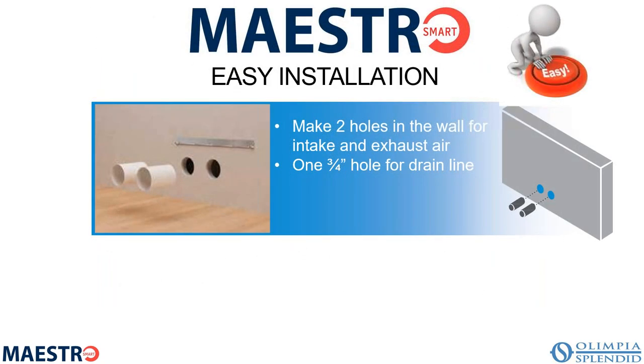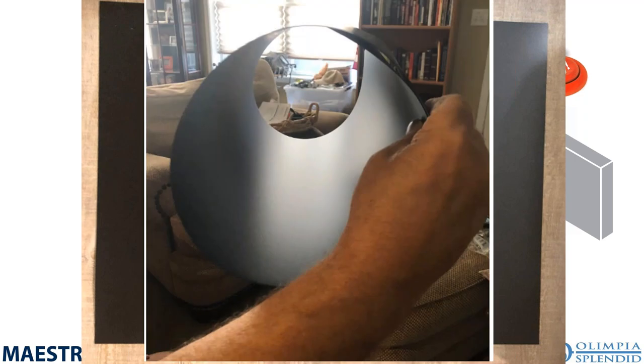So you make the two holes in the wall—one for intake, one for exhaust—plus the 3/4-inch hole for the drain, and then install the ductwork. This is what the ductwork looks like: a flat piece of plastic. Two ship with the unit, and you cut it to the thickness of the wall, maybe an inch and a half shorter. Then you roll it into a circle to form a duct, put a seam of tape along the top and bottom, and when installing make sure the seam is up top and the holes are drilled at a slight angle so any rain or water runs back out.